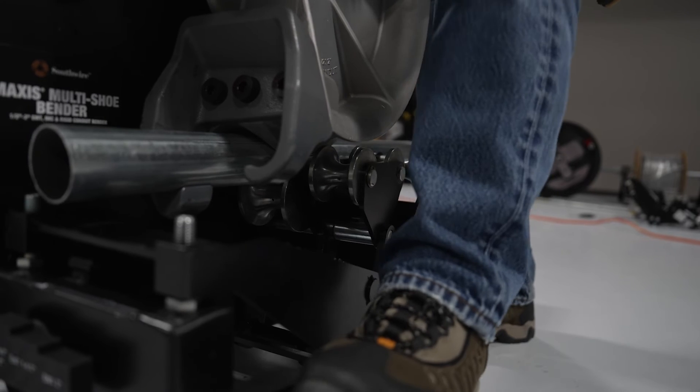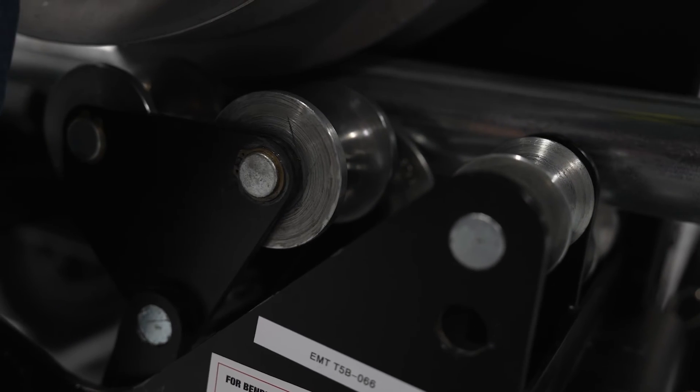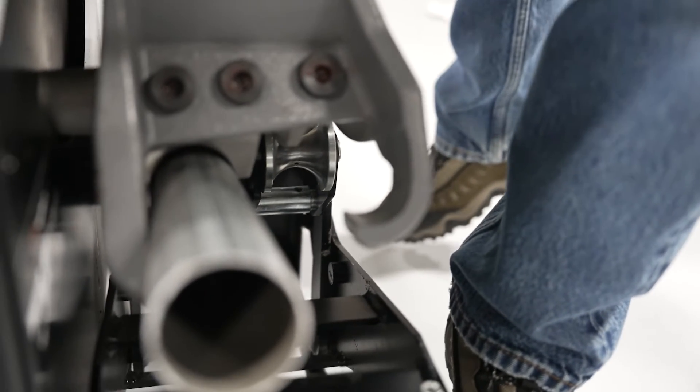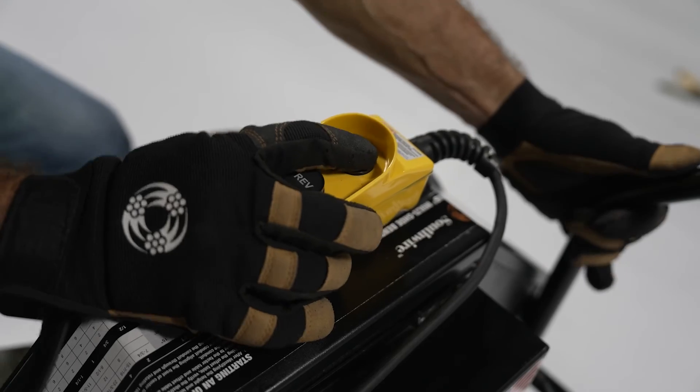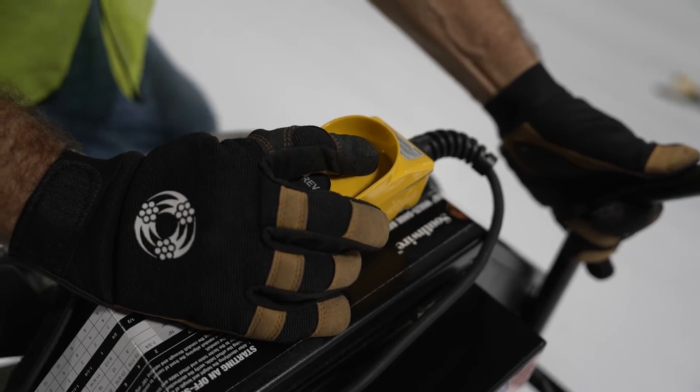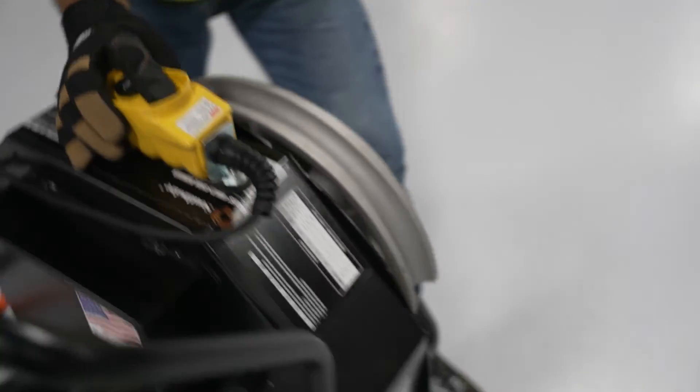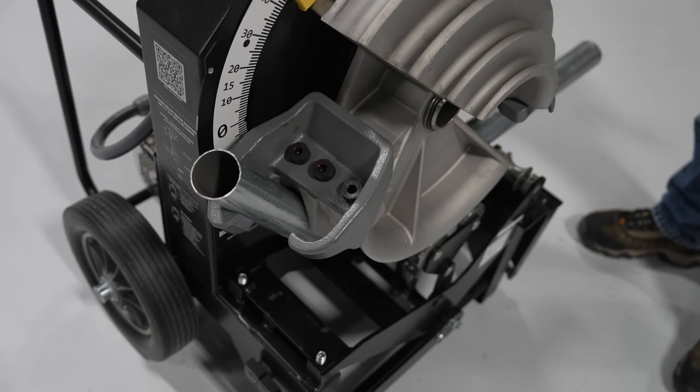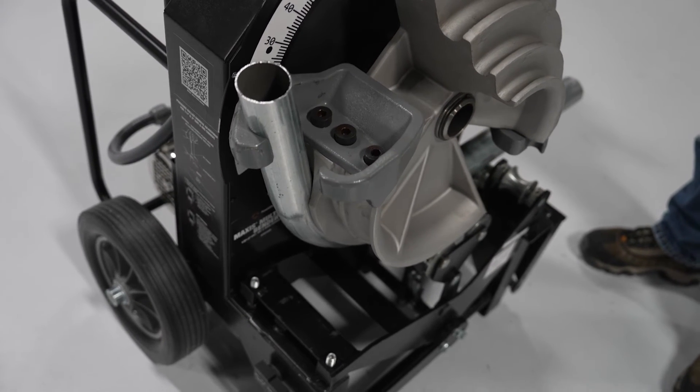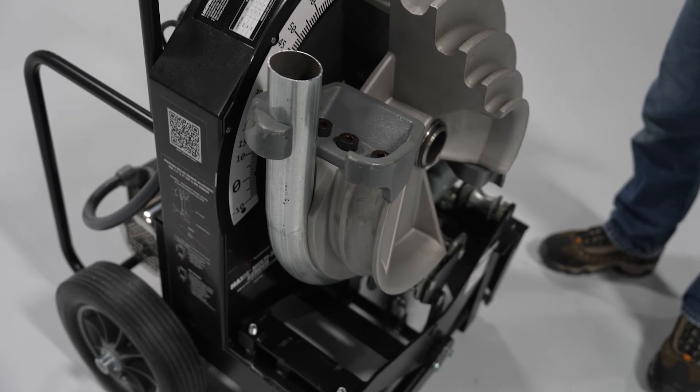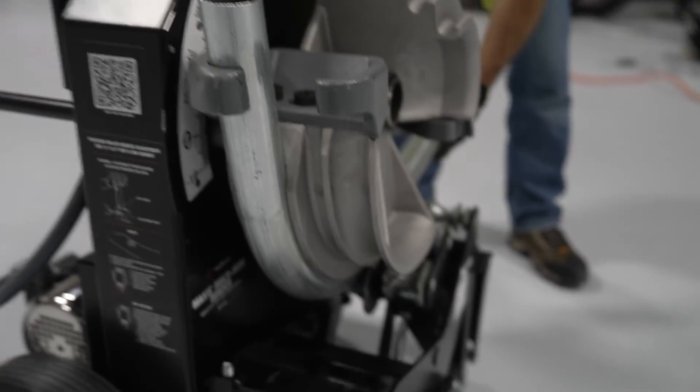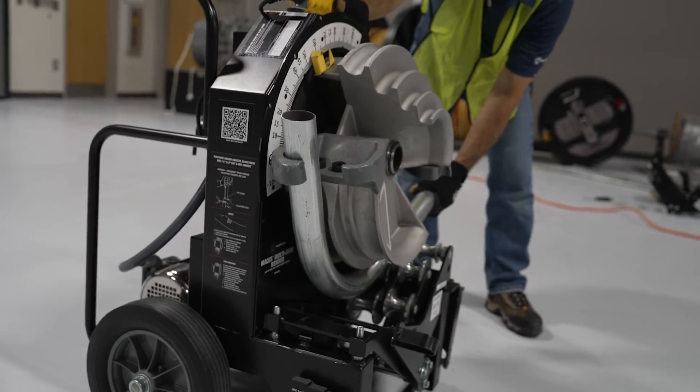Next, place your foot on the pressure pedal to bring both rollers into contact with the conduit. Start the bend by pushing down on the pressure pedal with moderate pressure. Press and hold the forward button on the pendant while maintaining pressure on the pedal. As the bend begins, the pressure rollers will rotate and roll into the fully engaged position. The pressure pedal should come into contact with the stop, and once the pressure rollers are fully engaged, you can take your foot from the pressure pedal and continue with the bend.